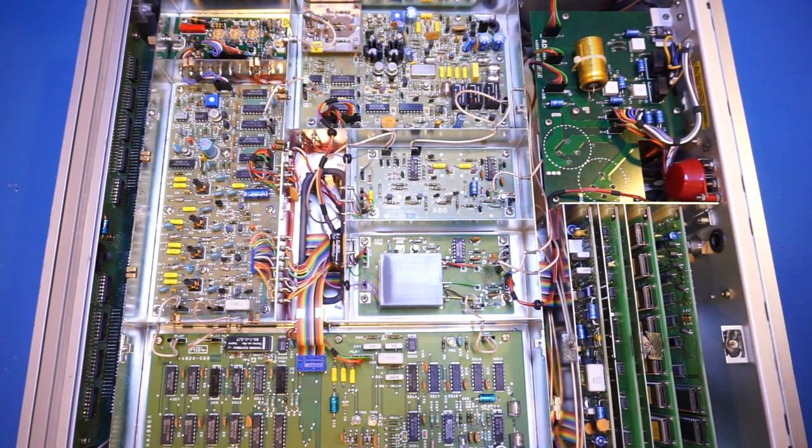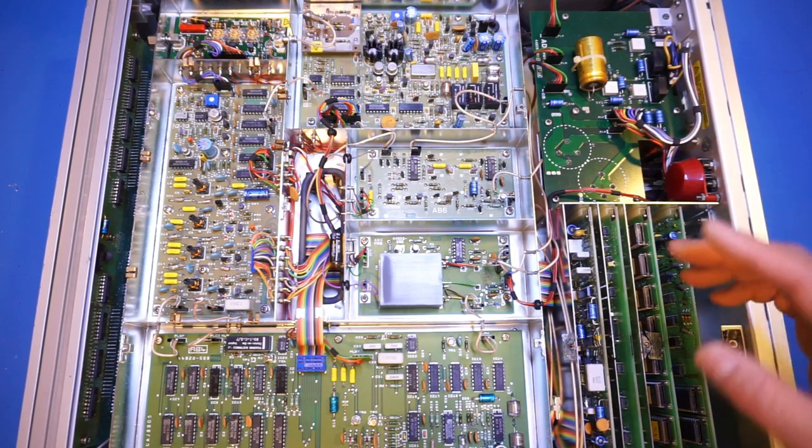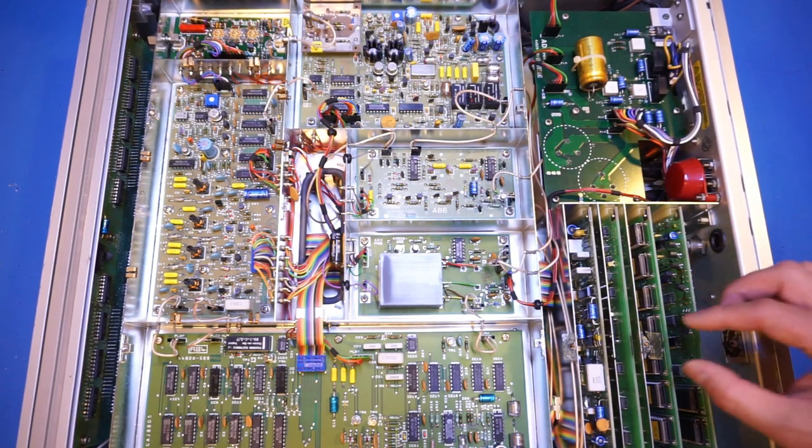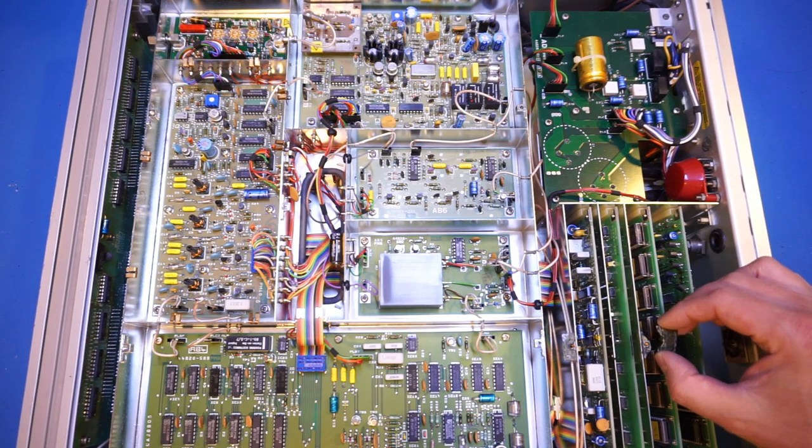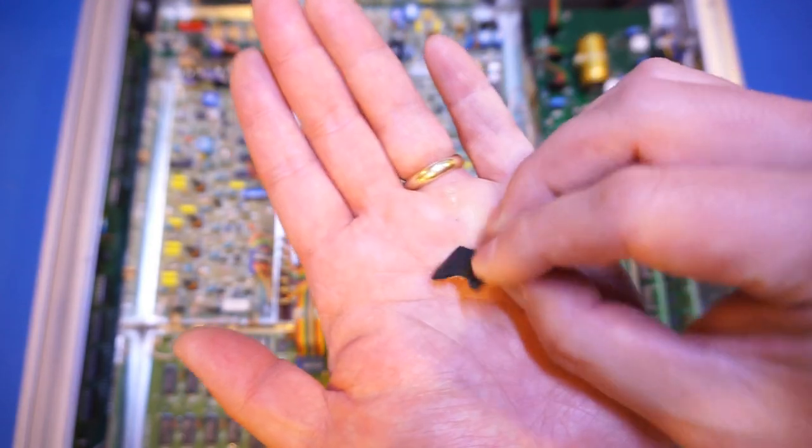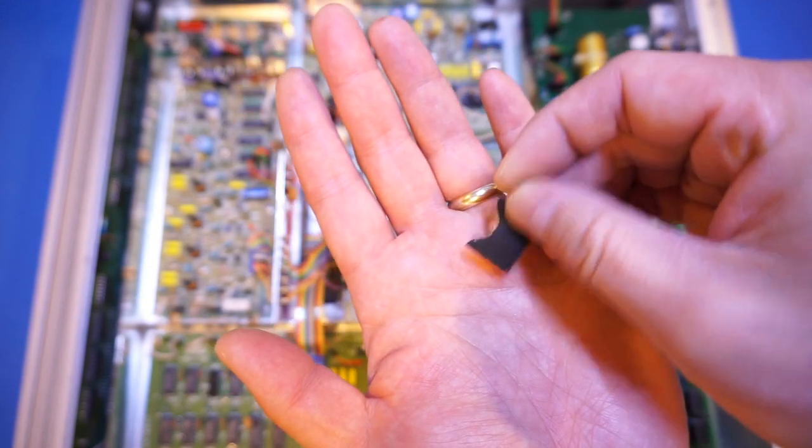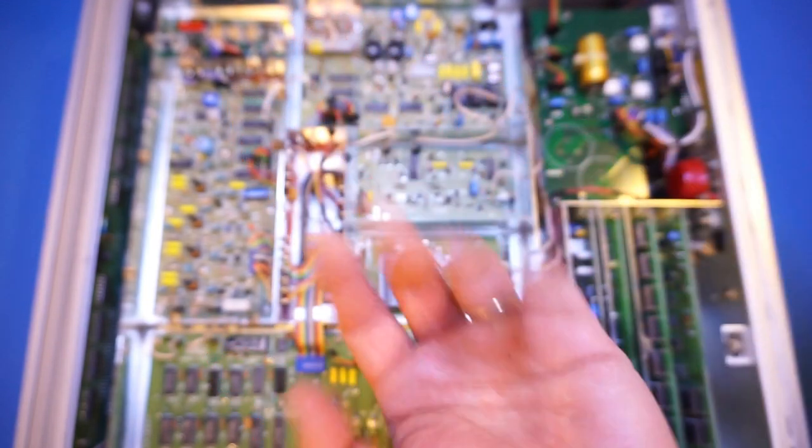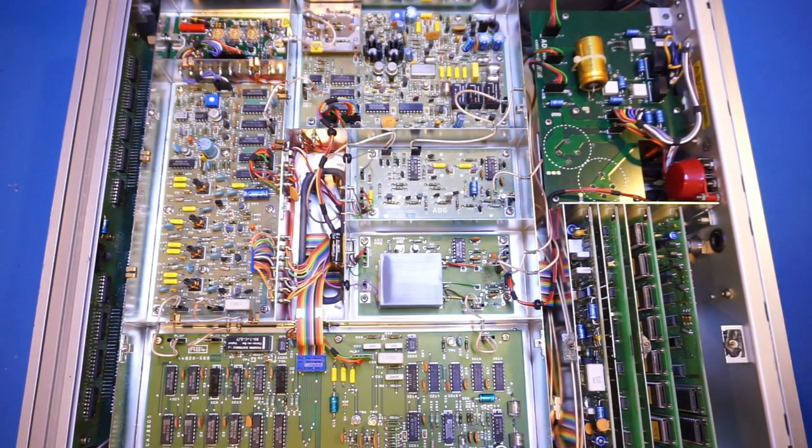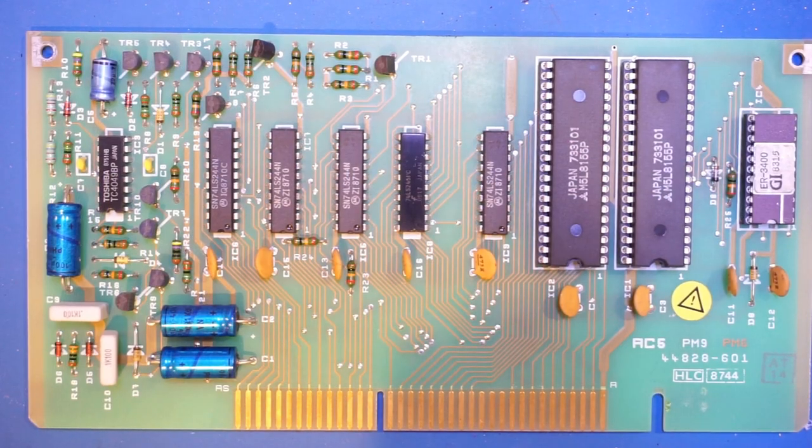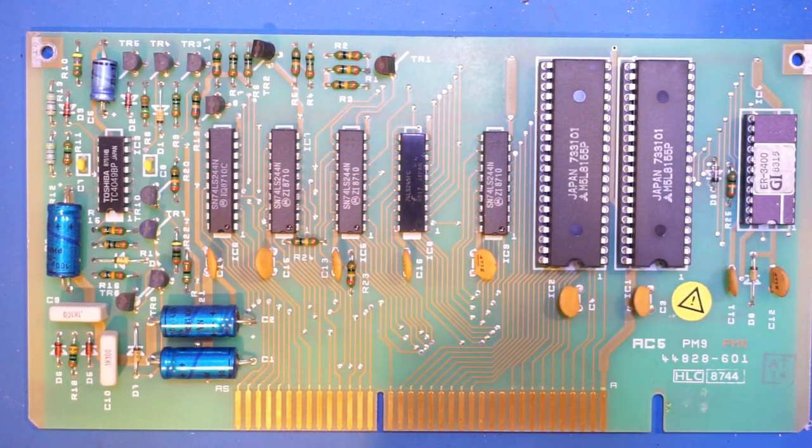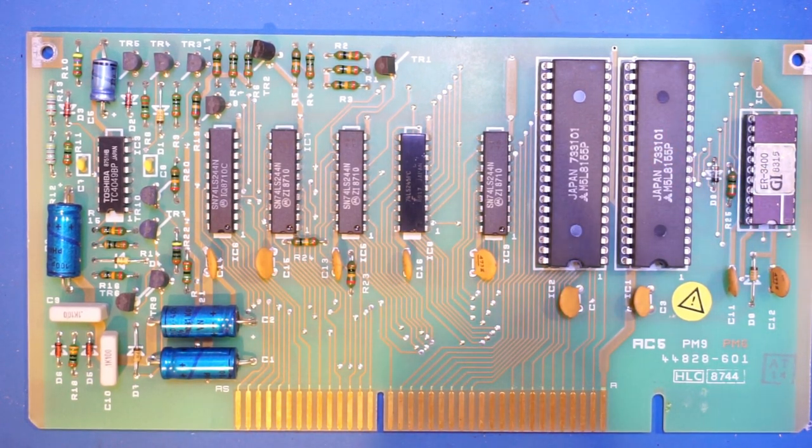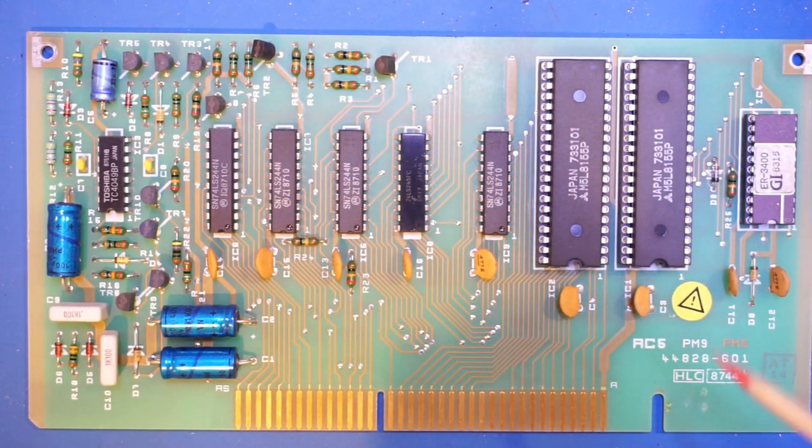It's interesting to see as these kind of instruments age, the plastic bars actually became very brittle. In fact, I was just touching this piece and as you can see, this piece totally crumbles and basically just comes right apart. That's something you need to pay attention to when servicing these kind of older units.